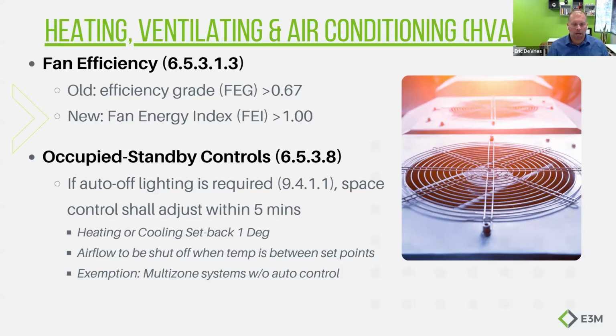Really every manufacturer out there has recognized this now. If you go onto a Greenheck or a Cook selection software, and you pick ASHRAE 90.1 2019, it's not going to spit out FEG for you anymore. It's automatically going to spit out FEI. So you're going to see changes to specs. You're going to see changes to equipment schedules to reflect this change.